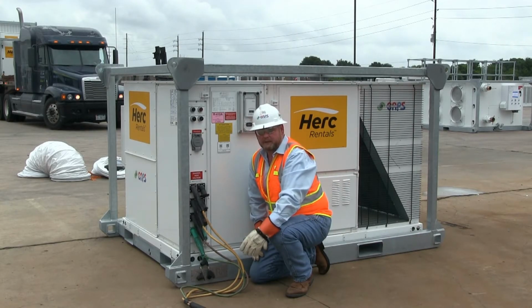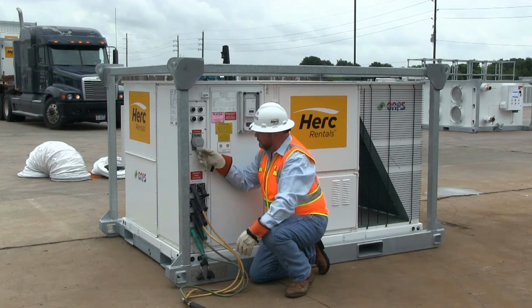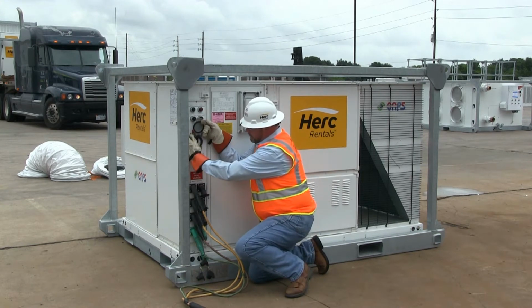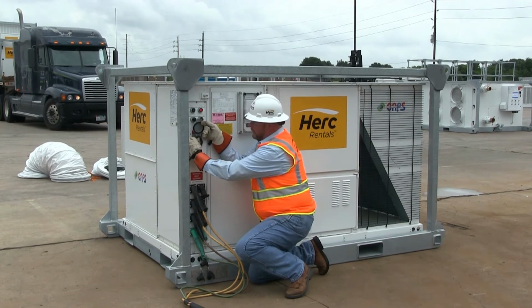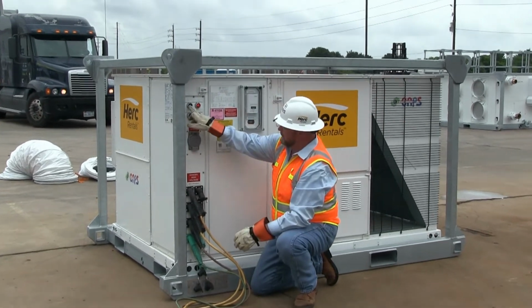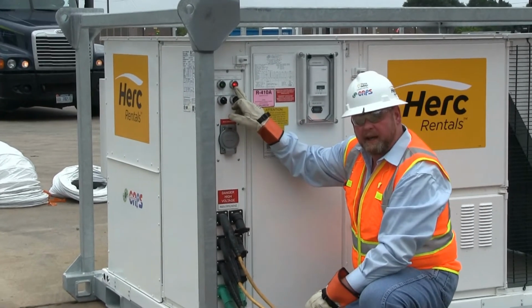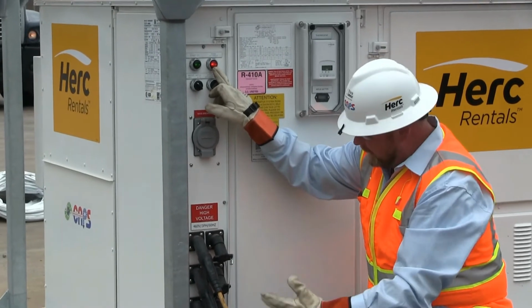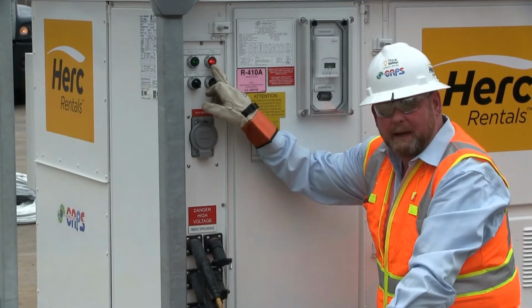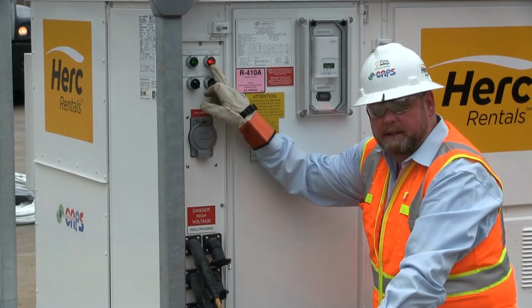Okay, we've energized our main power source. Now we're going to open up the unit mounted breaker. We're going to energize the power bit. The power lights come on, but you'll also notice that the phase incorrect lights come on. That indicates that two of our phases are backwards and the machine will not run in this condition.